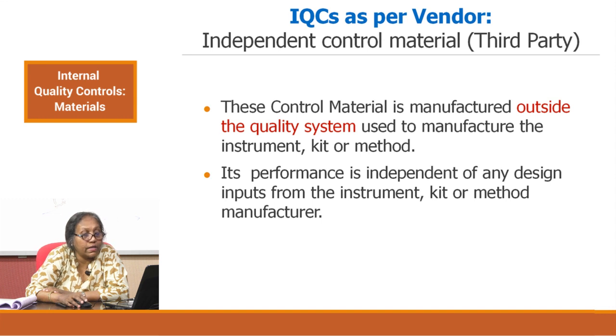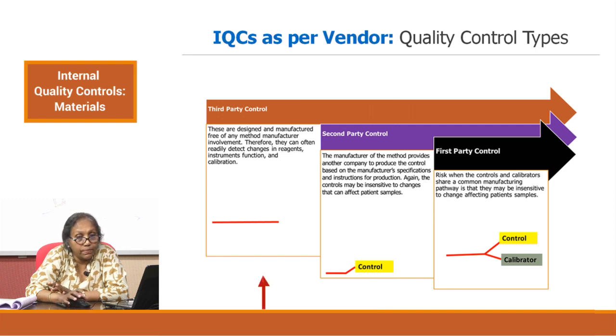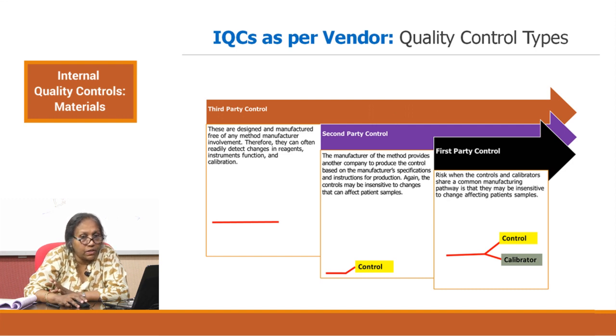The third party control's performance is independent of any design inputs from the instrument kit or method manufacturer. The first party control follows the same path as the calibrator and the equipment and reagent. In the second party control, the control is developed via a different path from the calibrator, but the reagent and equipment path are the same. The third party control is independent of any of the manufacturer's inputs, and therefore can readily detect changes in the reagents, instrument function, and calibration. Third party controls are by far the best detectors of errors in the analytical system and are always preferred if they are available.